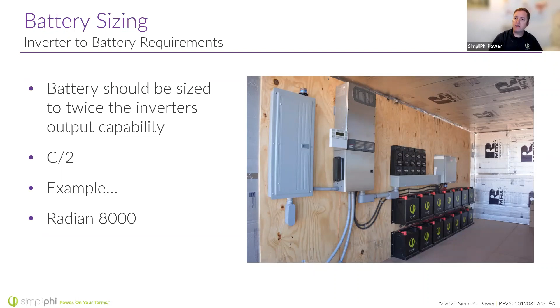There's only three of us here, so don't pull or push more power than what two or three of us can handle. When you're sizing for SimpliPhi, you've got a little more leeway. When sizing for the standard PHI batteries, I really want to see that C/2 rating. With charge controllers, like these Outback charge controllers, it's not as hard a rule, because we can program those charge controllers to limit their charging amps. You can't really program an inverter not to work at its full capacity. So again, C/2 rating, I want to make sure that's clear to everyone.